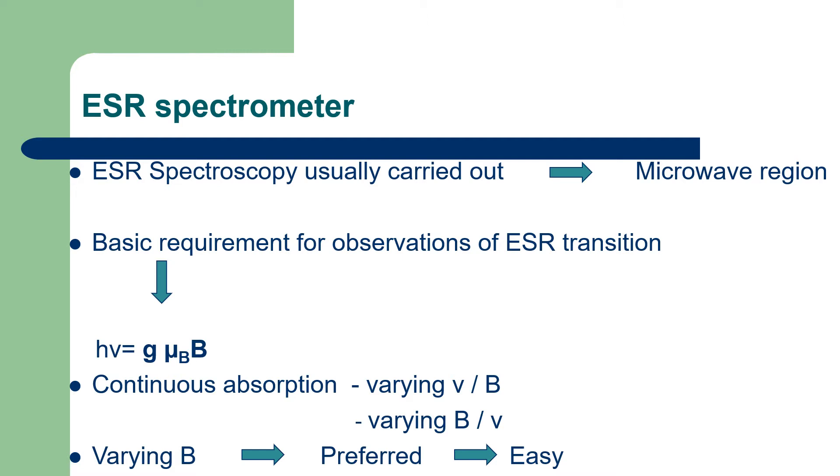The basic requirement for observing ESR transition is the resonance condition hν = gμB. We can attain this resonance condition by continuously varying the incident frequency ν and keeping the external magnetic field B constant. The second method is varying the external magnetic field B and keeping ν constant. The second method is easy because we can vary the external magnetic field easily, so it is preferred over the first one.